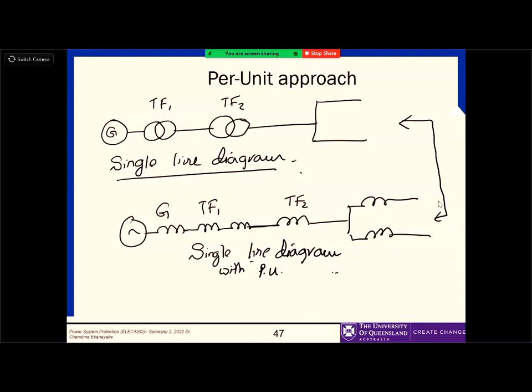The approach is that you need to specify something called the apparent power for the whole system. Let's say 100 MVA is the apparent power for the system, that defines the base power for the whole system. The second thing is you need to define the voltages. That voltage definition I'll come to later when we're doing calculations, there's a certain criteria for how we define the base voltage, which we'll discuss.